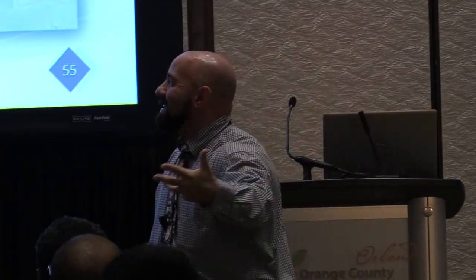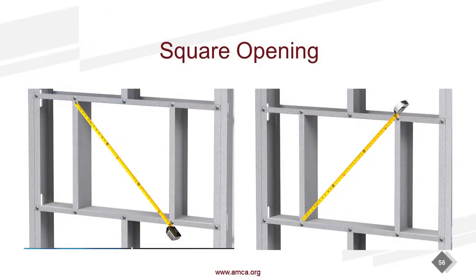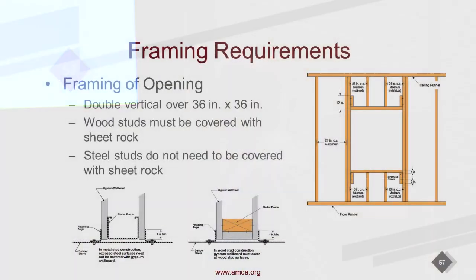And then, of course, like I said, it has to be installed properly. Take a curtain fire damper and install it upside down. You've met the code, you got a damper installed, but it's not installed properly, right? So here's our square opening. So again, we don't have a lot, we have a couple installing contractors. Call before you install. You don't have an opening that's built properly, don't stick a damper in it and go, hey, that barrier wasn't built right. Now you're gonna have to take that damper out. You could possibly damage it. You might need to reorder it, all right? So call before you install.